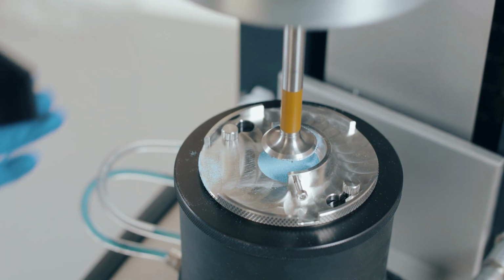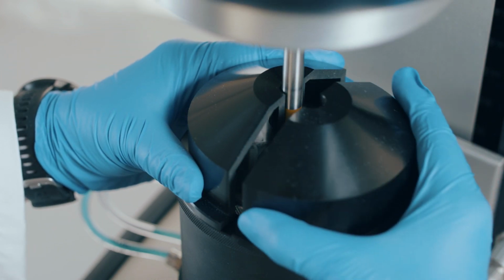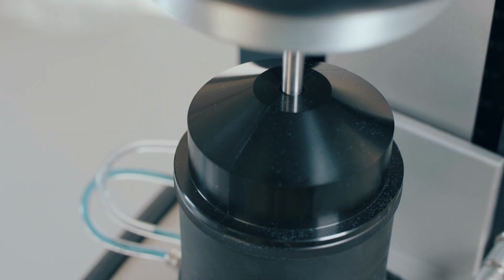Once the geometry lowers to the powder, the draft covers may be installed. The rheometer will then perform the shear measurements as defined in the test procedure.